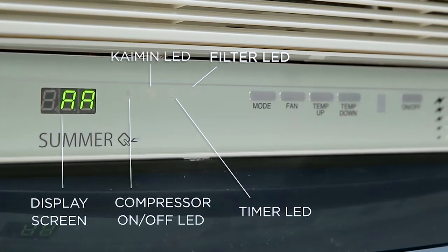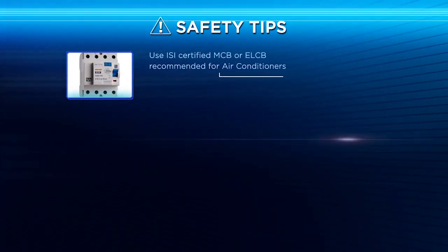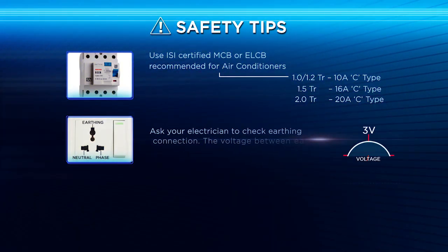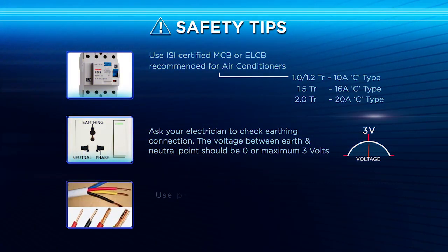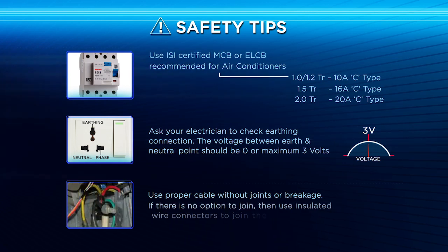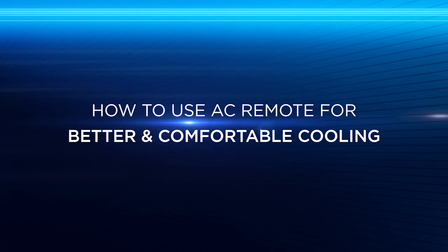Safety tips: Use ISI certified MCB or ELCB recommended for air conditioners. Ask your electrician to check the earth connection — the voltage between earth and neutral point should be zero or a maximum of three volts. Use proper cables and wires without joints or breakage. If there is no option, use insulated wire connectors to join the wires.